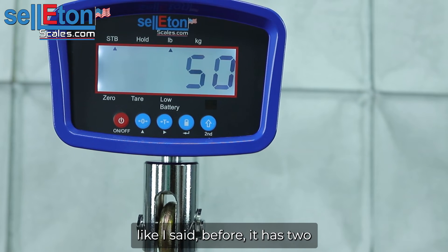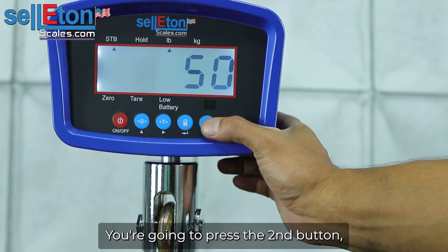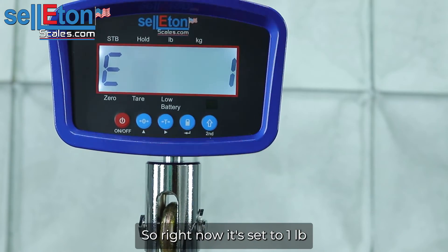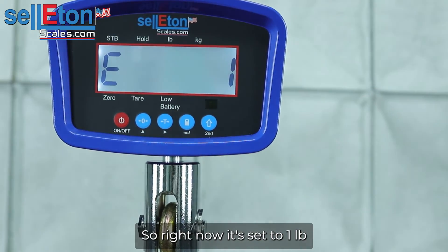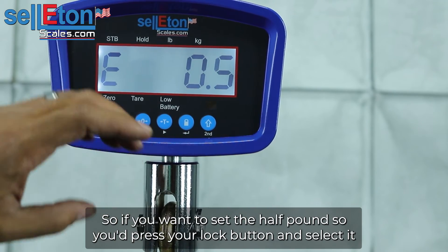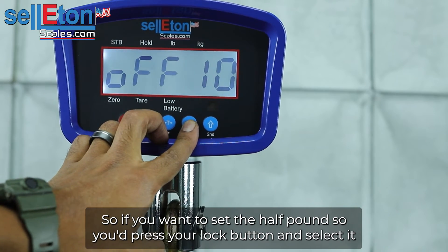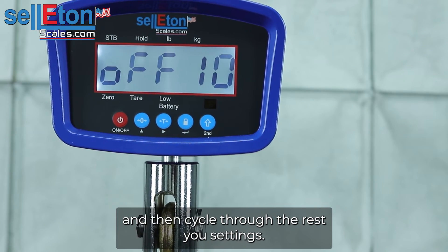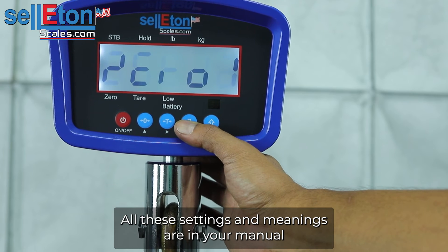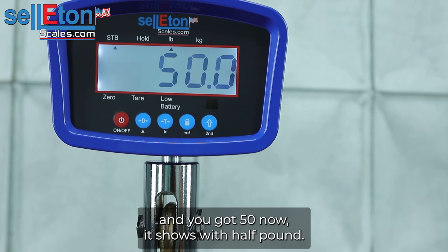Like I said before, it has two sets of accuracies. You're going to press the second button, then the lock button, and you'll see the accuracies it has. Right now it's set to one pound, and the other option would be half a pound. So if you wanted to set the half pound, you'd press your lock button, select it, and then cycle through the rest of your settings. All these settings and meanings are in your manual. And you got 50, it shows with half a pound.